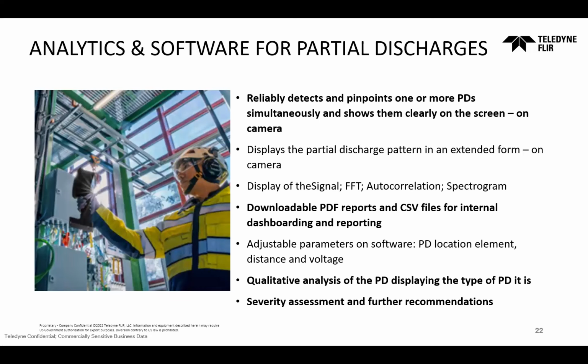So my recommendation: sometimes the camera is pinpointing something, for example in an isolator or somewhere, which looks like a partial discharge on the screen. In order to recognize this as a partial discharge, I always wait until the pattern is shown. There is a small box in the camera screen where you will see the pattern shown. You can actually extend it and see it there.